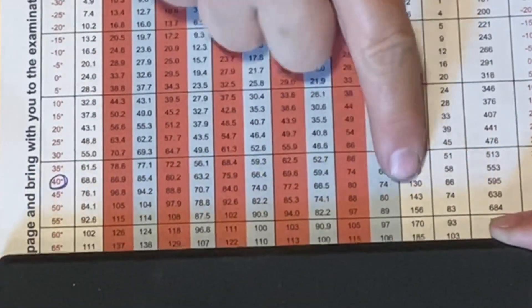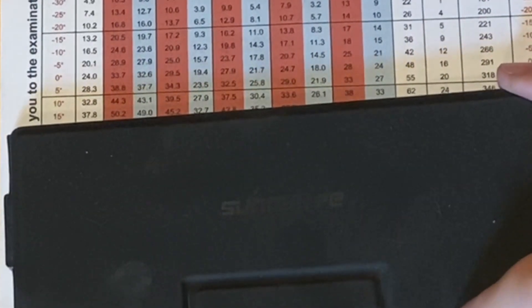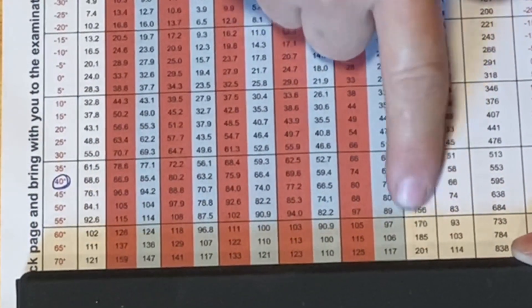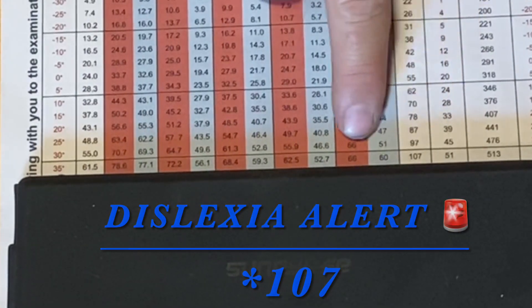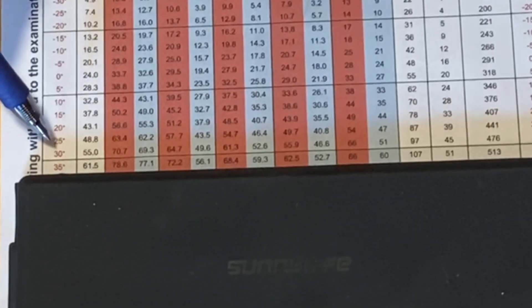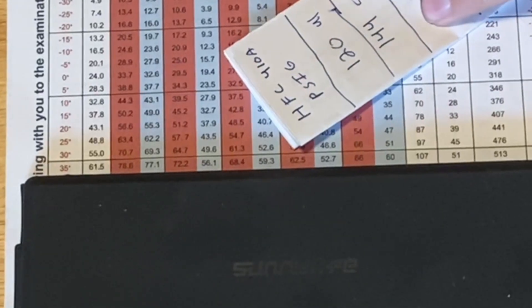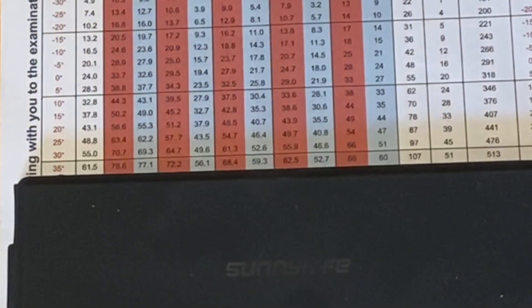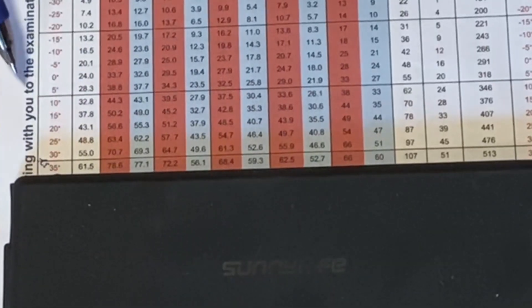And then we're going down to the next one is 102. So 102 is actually gonna be way up here. So we see we don't have 102. We have 97 or 107. So we look across there we're gonna be right between those two. And we see it's between 30 and 35. So that number is gonna be actually pretty close to 32 degrees Fahrenheit. So 32 degrees Fahrenheit that's actually our freezing point. So we're just gonna make a little note here of 32. We're right between those two numbers.